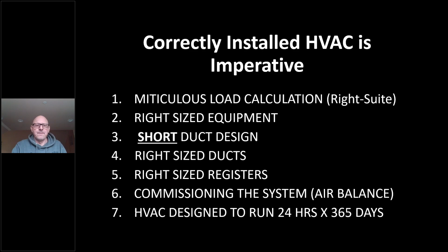And we have some data on this. So this is RightSuite. I use RightSuite, and I think Larry uses RightSuite. This is my design. It does the full load calc, as you can see here. This is a 1,250 square foot house. Our heating load for our design was 11,240, and our cooling load miraculously was under 7,000 BTUs. And any contractor that would come and look at this would say, I'm not putting this in, this is crazy. So not only does it do the whole house, it does room-to-room loads.